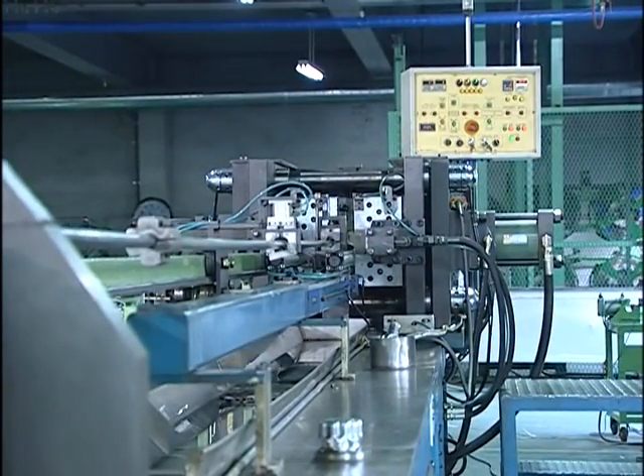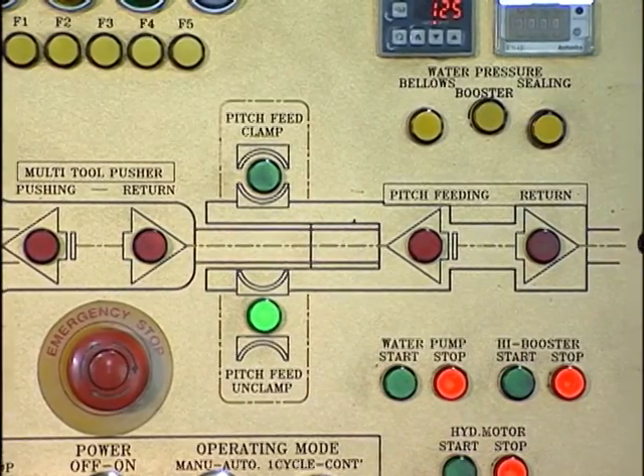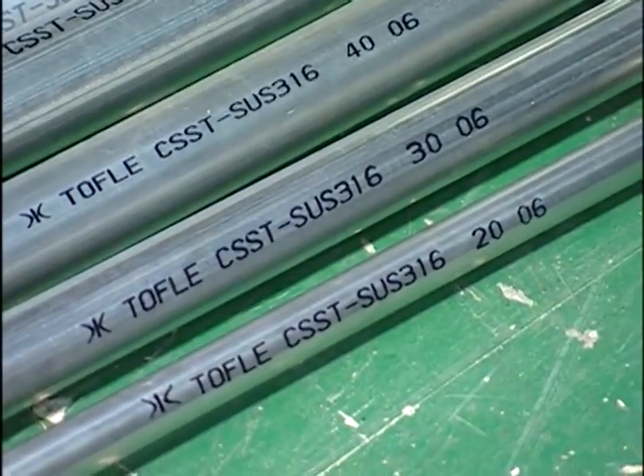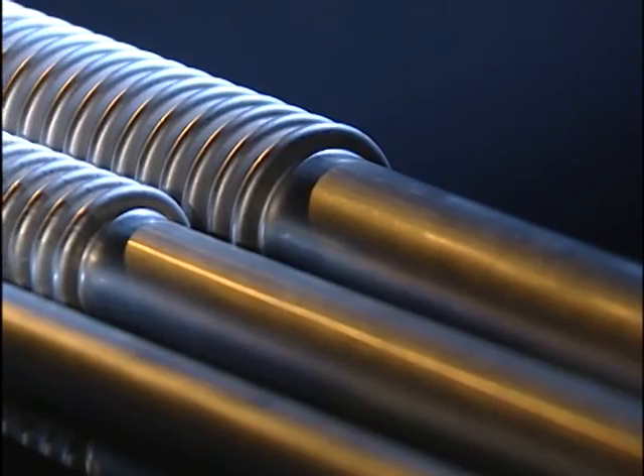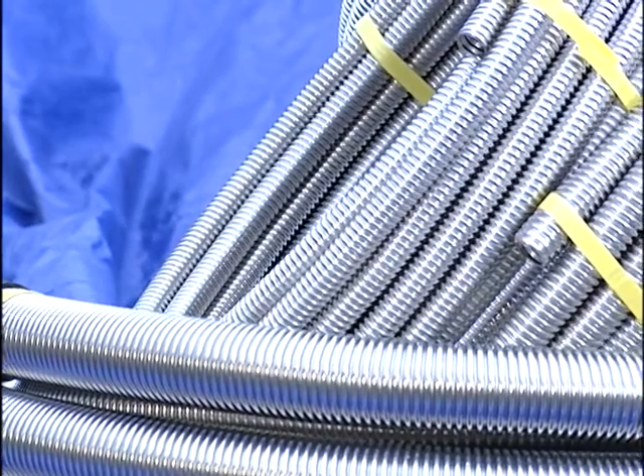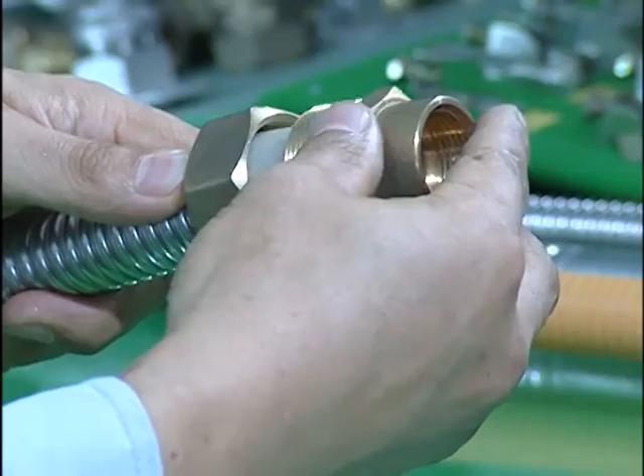The corrugated stainless steel tubes for city water system are hygienic and corrosion resistant high quality material for water systems. Made of AISI 304 or 316L steel, which is very durable and corrosion resistant, bellows formed and solution heat treated. The thicker bellows tubes are also used in vehicle steering wheel shafts and EGR pipes for shock absorption. They have excellent shock absorption qualities and can withstand earthquakes and ground subsidence, with no water leakage and can be bent with bare hands. The helical type corrugated tubes are supplied in endless roll type for the water piping system in buildings, with corrugation pitch widened to reduce fluid resistance, featuring screw connection of rubber packing type for connecting the fitting.